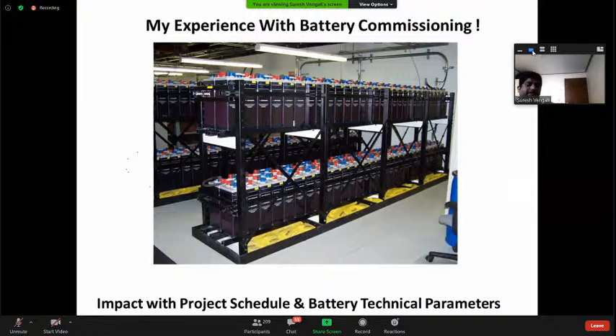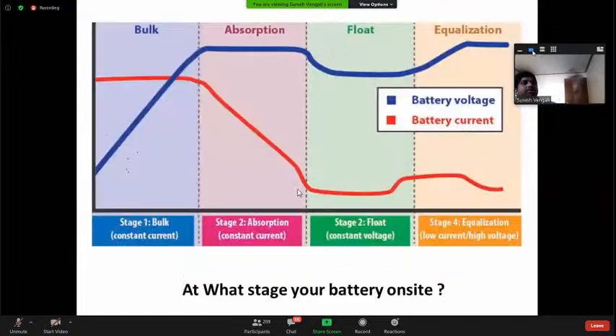Another important point: when the battery comes onboard, if you have long storage, the bulk and absorption phases are typically completed at the vendor's site. But if you don't have this, and it's been in long storage for more than 6 months, then you need to start from the beginning, meaning you need to go through all 4 phases on site itself. So the condition the battery arrives in, and how long it's been stored, are both very important.